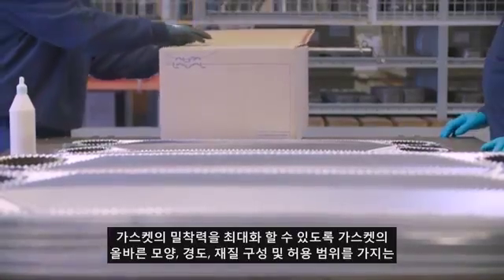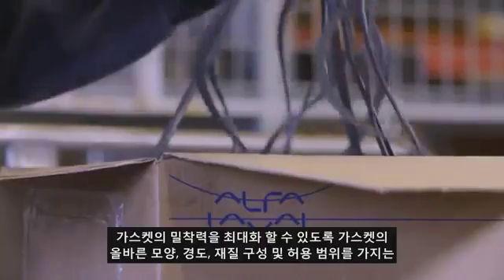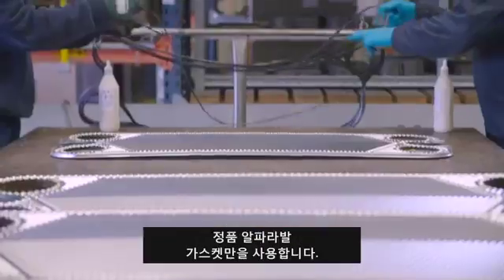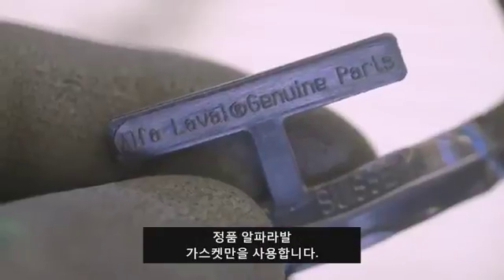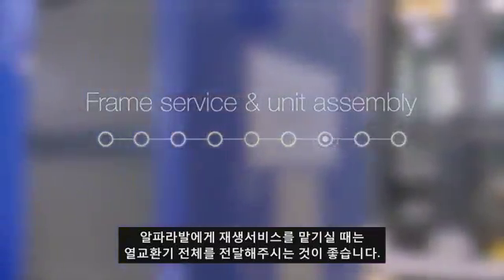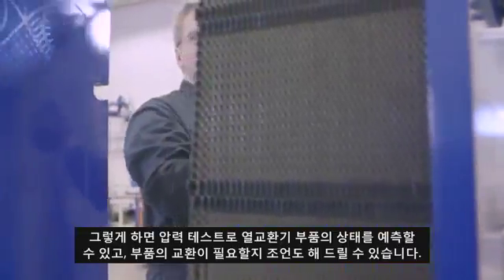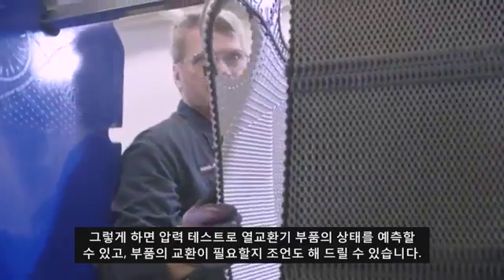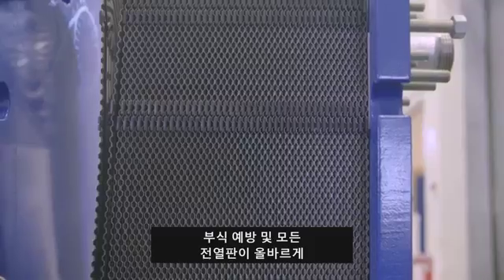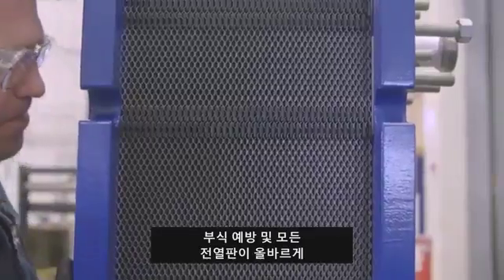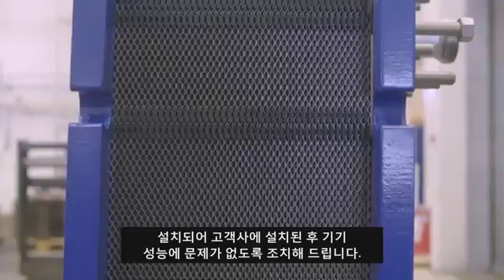To ensure the right shape of the gasket, the right hardness, the right compound, and the right dimensional tolerances, we only use genuine Alfa Laval gaskets. And that helps you to avoid premature leakage, or even worse, damaging the plates. We prefer to receive the entire unit when you service equipment with us. By doing so, we can inspect the pressure-retaining parts and advise on replacement needs. We can restore the corrosion protection. We can also make sure that all the plates are installed in the right order to get you the right performance when the unit is back.